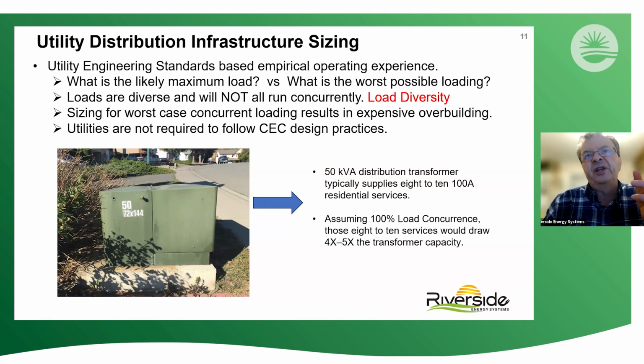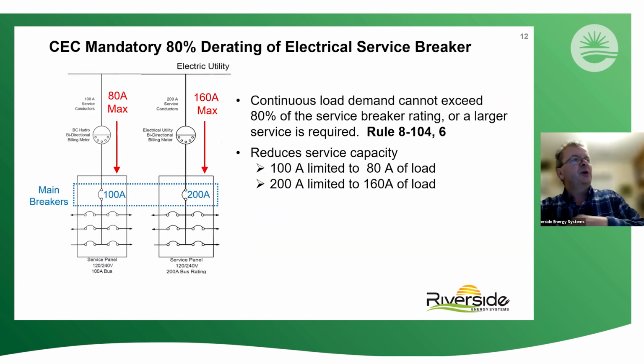This is inherently the trouble, because behind the meter, we're forced to comply with Canadian Electrical Code. In front of the meter, engineering standards and utility standards apply, which are not the same as CEC. So first up, we have to derate our main breaker, main fuse. So this means that our 100 amp service really can't deliver more than 80 amps if it's going to be compliant. And same, a 200 can only deliver 160. This is Rule 8-104, Part 6.